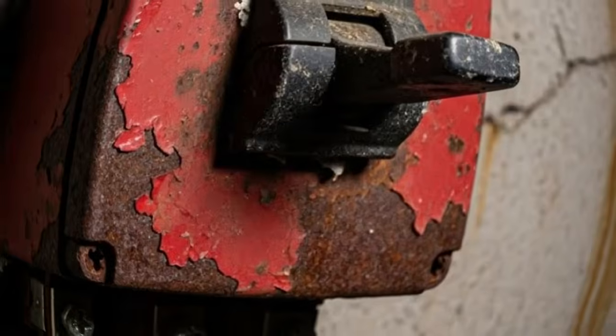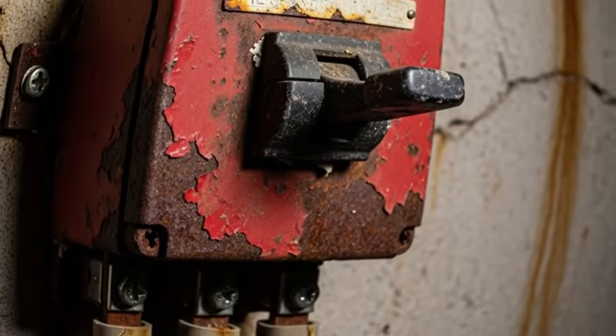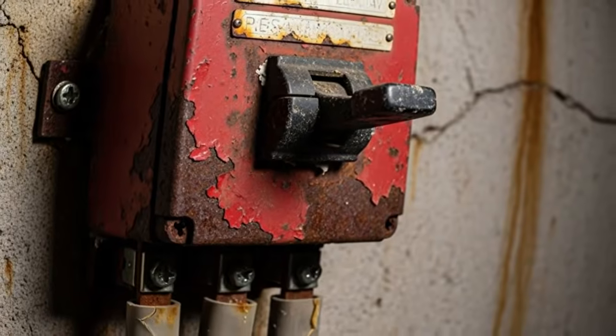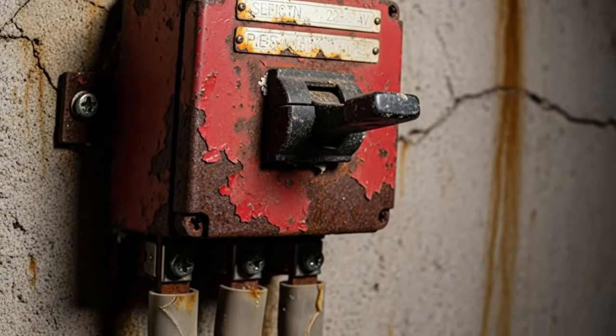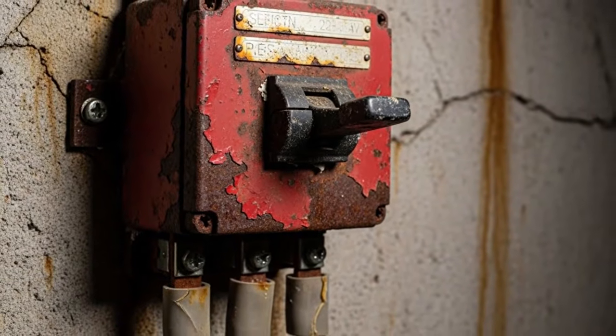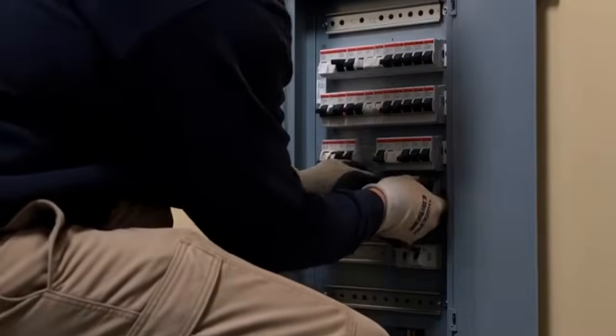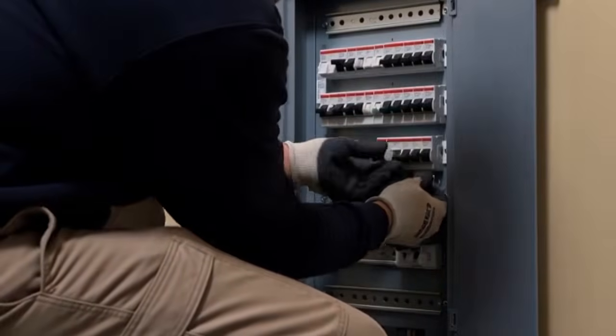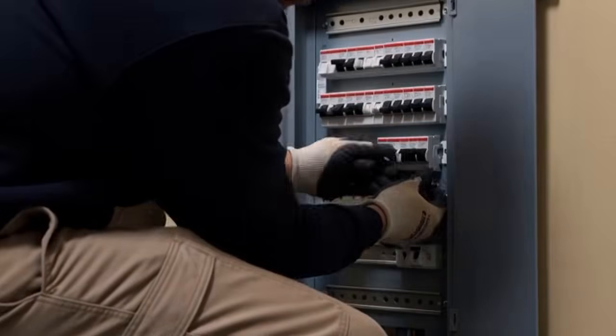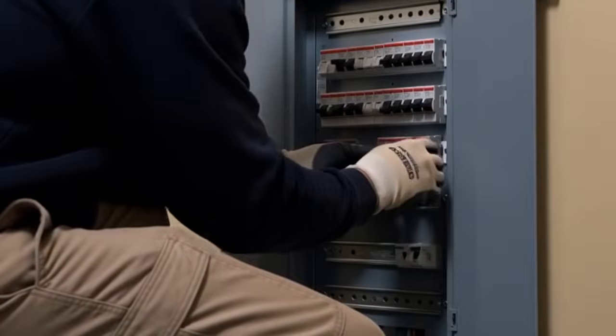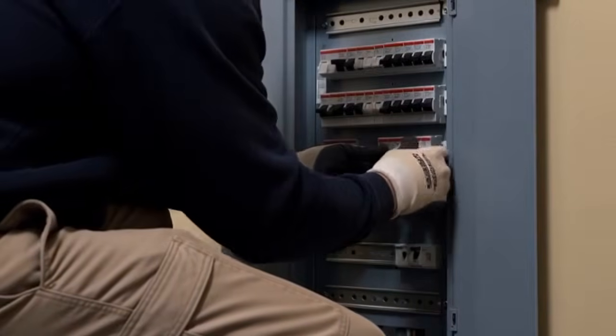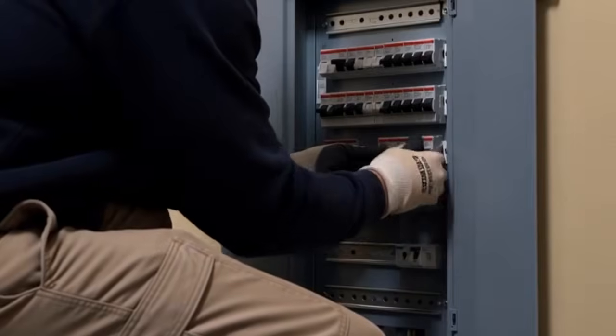If a breaker is more than 20 years old, has tripped numerous times over its life, or shows any signs of physical damage, the breaker itself may need replacement. However, breaker replacement should only be performed by someone qualified to work inside an energized electrical panel. The bus bars remain hot even when individual breakers are off.